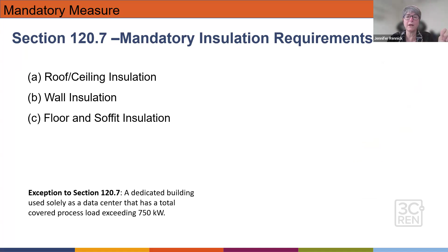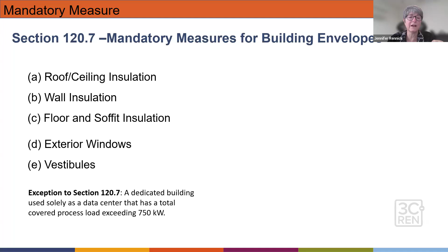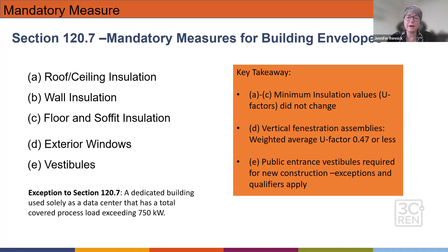For the section that was called 120.7, mandatory insulation requirements, there were just three things: roof, ceiling, wall, floor, soffit - pretty straightforward, and those mandatory requirements didn't change. But under the 2025 code, it got a new name: mandatory measures for building envelopes. Two sections were added: exterior windows and vestibules. The main takeaway is there's a weighted average U factor you have to meet for fenestration now, and public entrance vestibules are required for some occupancy types now.